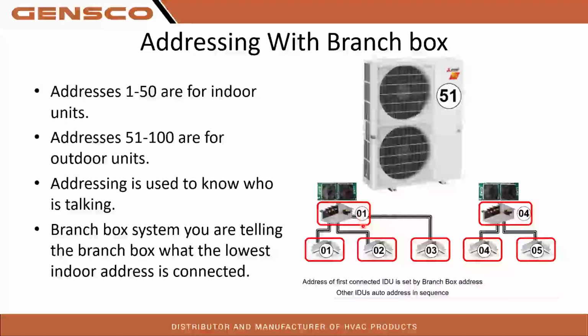So if you have a 5-port branch box and a 3-port branch box, and the 5-port is your first one and you are using all 5 ports, then your second branch box would be address 6. So just count how many heads you have on the first branch box, add 1. That's your address for the second branch box. Hopefully that answers that question.